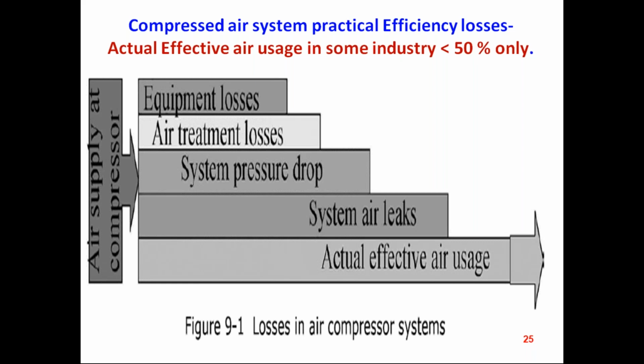So one is the equipment loss, then comes the air treatment loss. The air treatment loss is more in many of the machines or many of the industries than the compressor loss. The system pressure drop is an indication of where the pressure loss is happening, where the flow is more. Is it due to leakage or due to equipment consumption? Normally it comes due to leakage only. In many of the industries they report 30 to 50% goes away by leakage only. The effective air usage in the given industry is less than 50% because of leakages and abnormal deviations in the usages.